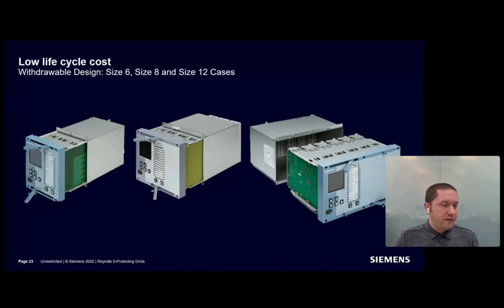The relay element is secured by locking levers and retaining screws. So you have the front screws and one at the rear. The Reyrolle protection devices are available in 3 case forms, which are suitable for panel or rack mounting. You see here size 6, size 8 in the middle, and size 12 on the right-hand side. The case size is determined by the number of binary inputs and outputs, and any additional arc flash input module and temperature sensor inputs.